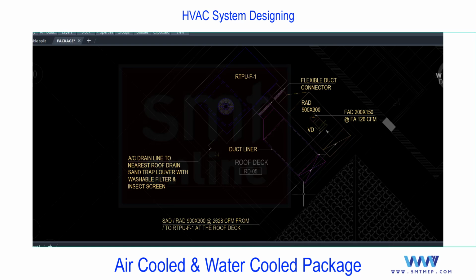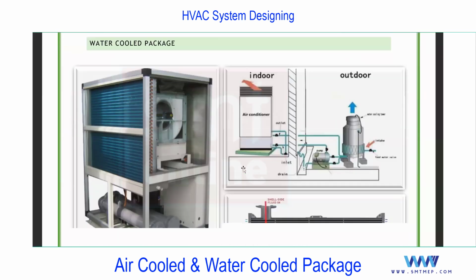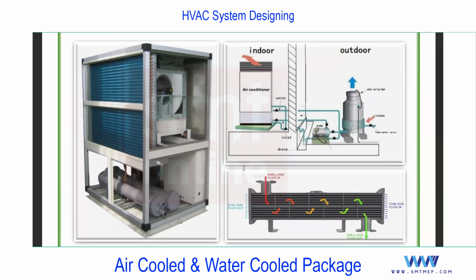Next, let me continue with the water cooled package. In the water cooled package, the condensing side is different. The condensing unit is cooled by water using a shell and tube condenser, which cools the refrigerant flowing in it, and that water we are going to cool by using a cooling tower. So try to understand only the condensing side circuit. The rest of the thing is the same.